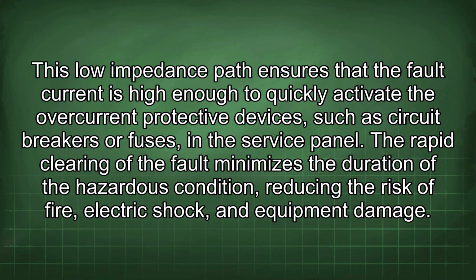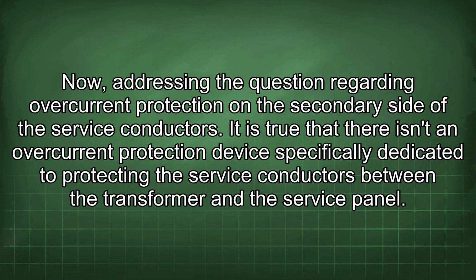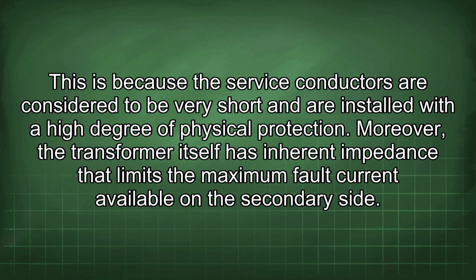The rapid clearing of the fault minimizes the duration of the hazardous condition, reducing the risk of fire, electric shock, and equipment damage. Now, addressing the question regarding overcurrent protection on the secondary side of the service conductors. It is true that there isn't an overcurrent protection device specifically dedicated to protecting the service conductors between the transformer and the service panel. This is because the service conductors are considered to be very short and are installed with a high degree of physical protection.